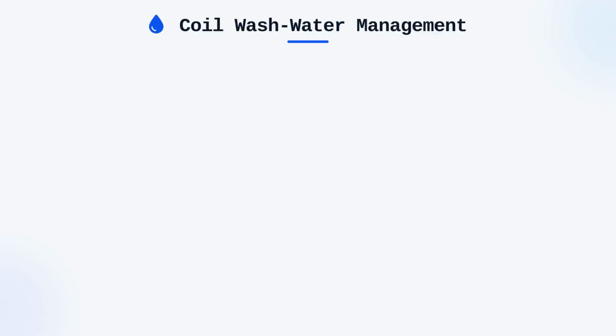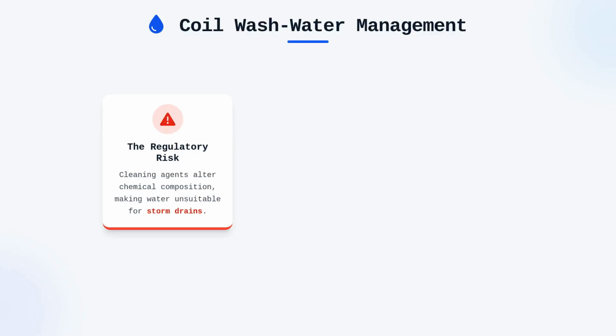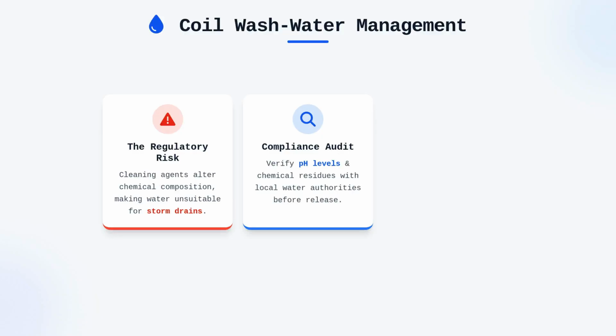The discharge of coil wash water represents a significant regulatory bottleneck that requires careful attention to local environmental laws. When you clean coils, you are likely using cleaning agents that alter the chemical composition of the water, making it unsuitable for discharge into a typical storm drain system. Most municipalities have strict sewer discharge laws prohibiting the introduction of chemicals, heavy metals, or oils into the public wastewater infrastructure without prior treatment. You must check with your local water authority to determine the permissible parameters for pH levels and chemical residues before you release any wash water.